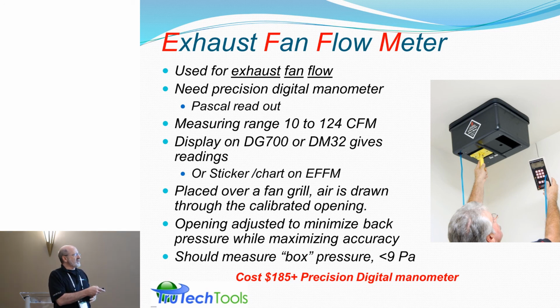This is the one where I was laying it on top of a grill, and then when I taped the seal down, I got a change in it. So I learned a lesson. You really have to pay attention to air sealing. Even with the lowest of flows, air sealing is critical. If the box pressure goes to 9 or above, you're in a no man's land where you're no longer getting a CFM calculation from it.